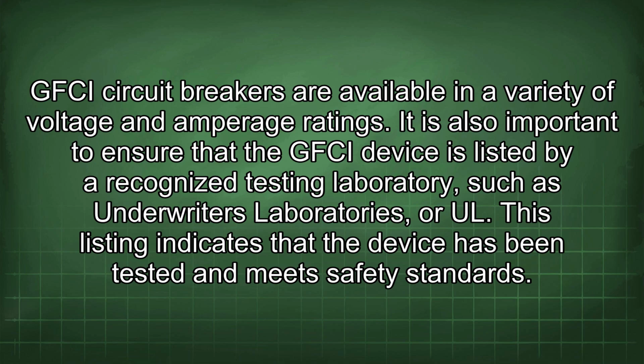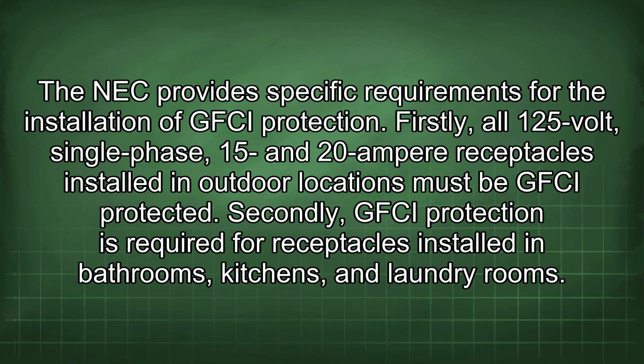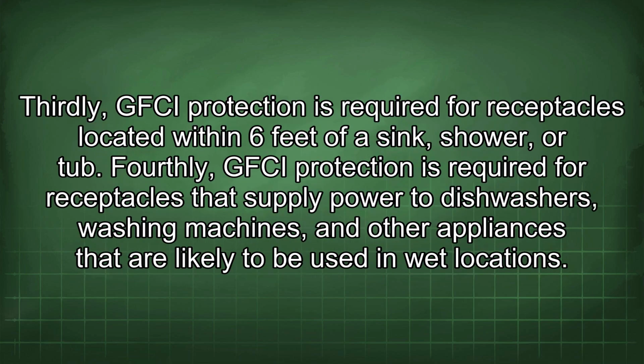It is also important to ensure that the GFCI device is listed by a recognized testing laboratory, such as Underwriters Laboratories, or UL. This listing indicates that the device has been tested and meets safety standards. The NEC provides specific requirements for the installation of GFCI protection. Firstly, all 125-volt single-phase, 15 and 20 ampere receptacles installed in outdoor locations must be GFCI protected. Secondly, GFCI protection is required for receptacles installed in bathrooms, kitchens, and laundry rooms. Thirdly, GFCI protection is required for receptacles located within 6 feet of a sink, shower, or tub.